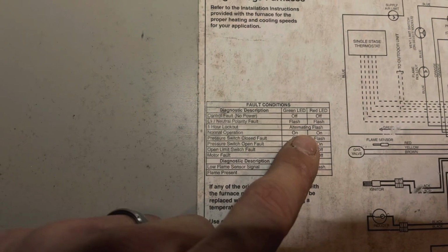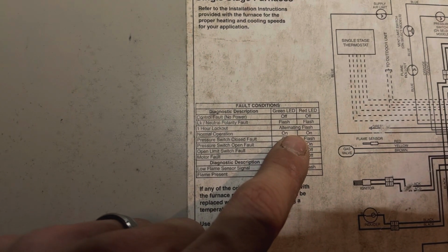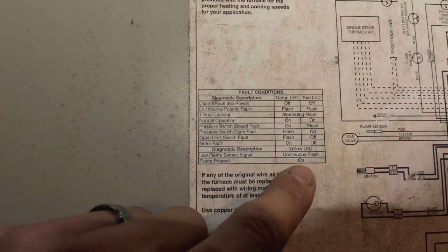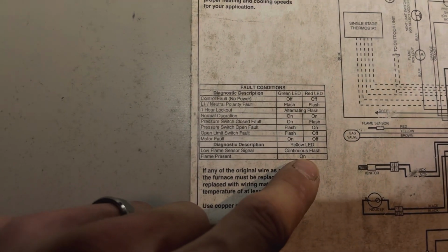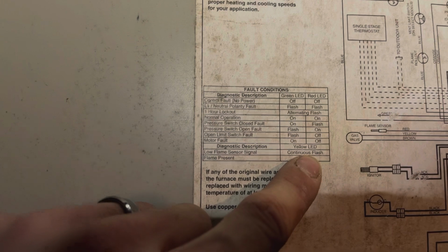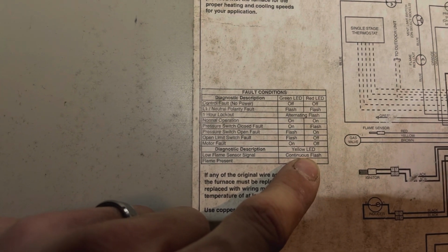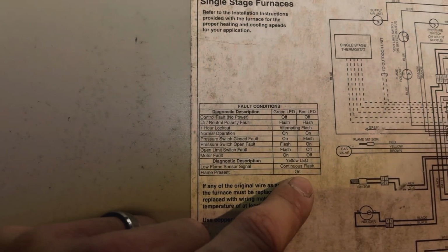So you can see here now, we've got a green light, red light on, and yellow light on. So what does that mean? Well, you can see here, fault conditions, normal operation, on, and down here, flame present, on. Continuous flash means low flame sensor signal. So there's another issue you could look at.